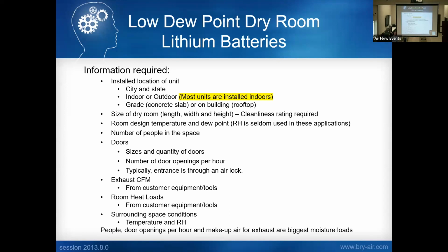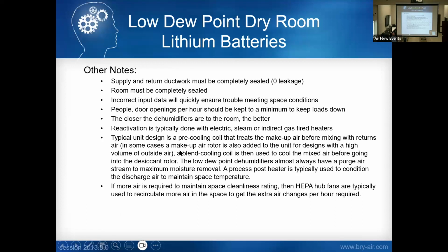So all entrances are through airlocks that are timed so that you can't open the inside and outside doors at the same time. Walter, you speak about the envelope and all of the infiltration and permeation. One of the big frustrations I've had with my customers is that the end user looks at it as, okay, this isn't just a piece of equipment. They have to make a significant investment in shoring up the infiltration coming into that room. How critical is that for your design process?